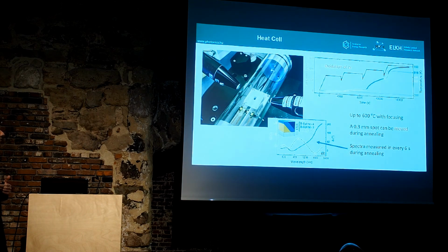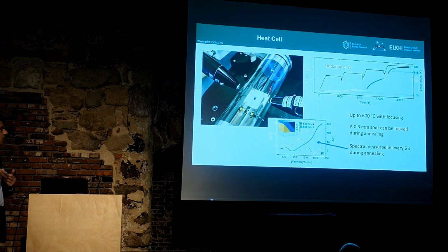The second example is also a non-destructive, in-situ measurement. This is a heat stage, a ceramic plate. You can heat it up to 600 degrees C, put the sample on top, and focus the light inside this glass tube. The spot size is below 1 mm, and you can even move the spot along the axis of this tube. This also has 1 second time resolution.